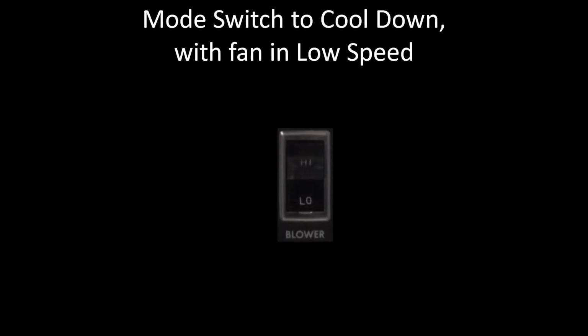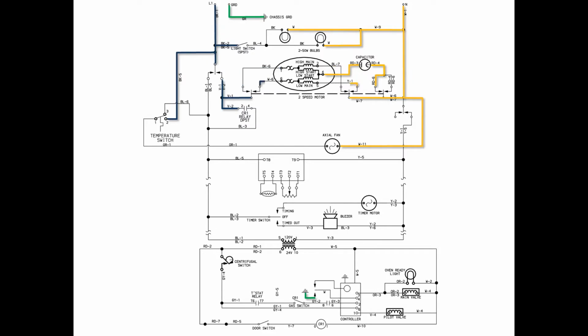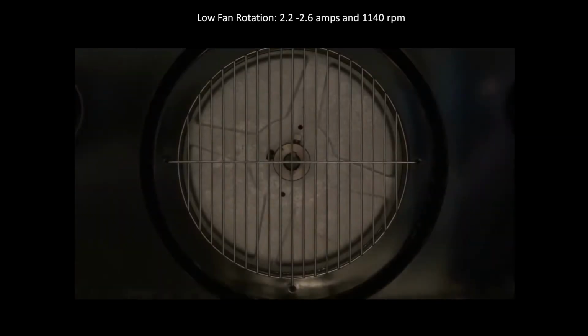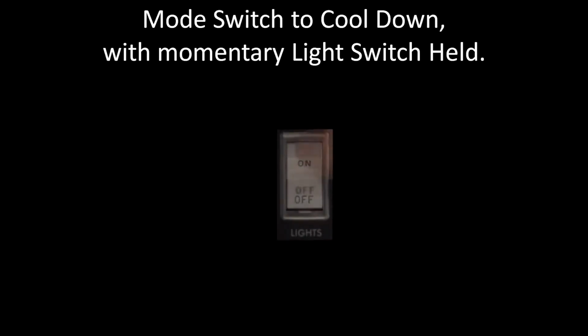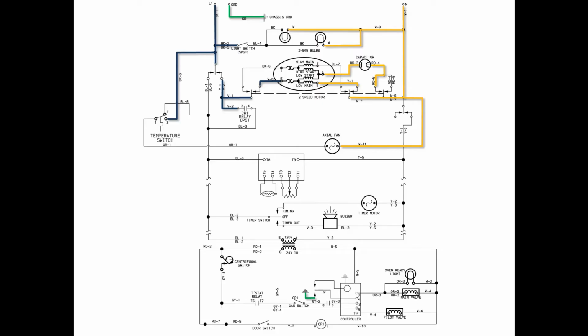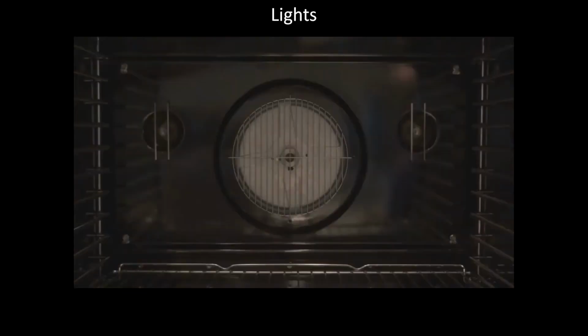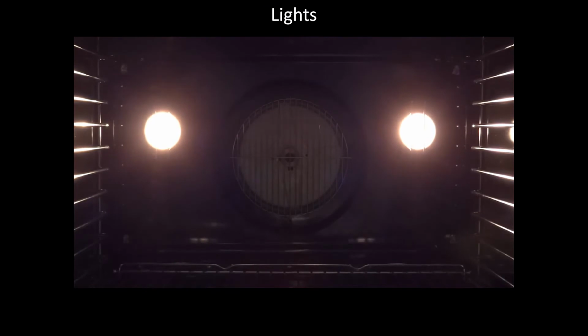While still in cool down, we will switch the blower to low speed. The voltage switches to the low winding of the motor. Low fan runs at 2.6 amps and 1,140 revolutions per minute. Next, we will hold the momentary light switch in the on position to turn on the lights. This feeds voltage to the lights. They're located in the rear of the unit.